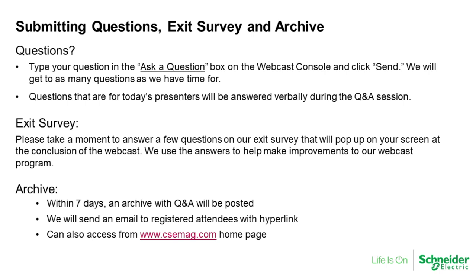Next question: Could you please discuss retrofit options? Retrofit means adding sensors or an arc flash system to existing switchgear. There are relays that can be easily added to existing switchgear by placing sensors in different areas and connecting them to the device. We're not going to touch anything else in the system. But remember, the major factor is how fast the breaker operates. If you have a very slow breaker, even if we detect the arc in 2 milliseconds with a 10-cycle breaker, it won't help much. So in a retrofit scenario, you may need to replace the breaker with a faster one along with the faster arc flash detection system.